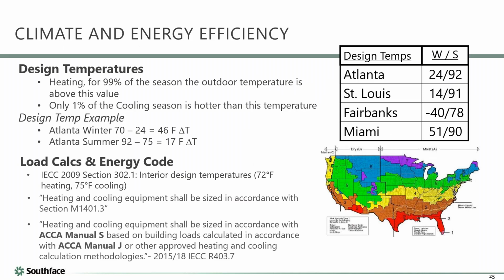It all starts with this idea of design temperatures. There are indoor design temperatures, which for the most part we choose 70 in the winter and 75 in the summer. Those are the defaults. That's what we're trying to make the indoors be in different seasons. And then there are outdoor design temperatures, which are a function of the climate that city is located in. If you do the math, there are about 8,800 hours in a year. If you do 365 times 24, you'll get about 8,760, I think. So about 8,800 hours. Say a fourth of that is heating and a fourth is cooling, but let's be generous and make the math easy. Let's say 2,500 hours is air conditioning and 2,500 hours is heating.